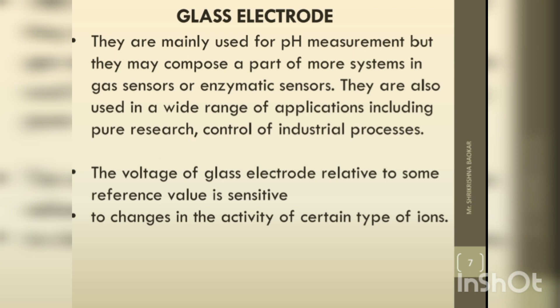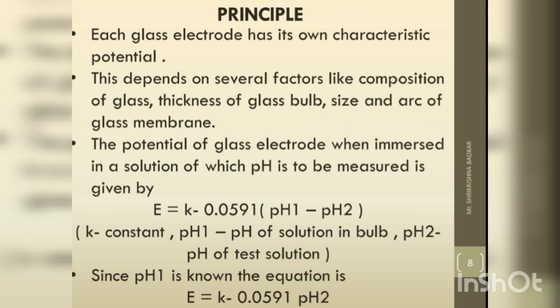The voltage of the glass electrode relative to some reference value is sensitive to changes in the environment and the activity of certain types of ions. Each glass electrode, being a pH-sensing electrode, has its own characteristic potential because of the ion exchange nature of the glass membrane. This depends on several factors like composition of glass, thickness of glass bulb, size, and area of the glass membrane.